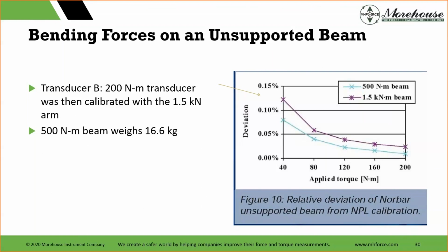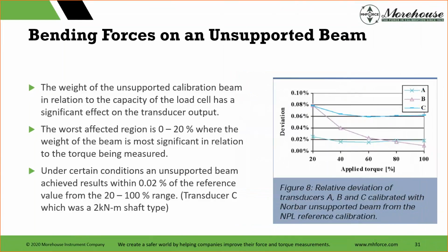That's the weight of that beam. That's when we go back to the types of standards. It's where we're going with supporting a beam, which takes a lot of this away. So now let's look at the weight of the unsupported beam in relation to the capacity. The load cell has a significant effect on the transducer output. Now we're back to that original. The worst affected region is 0 to 20%, where the weight of the beam is most significant in relation to the torque being measured. Under certain conditions, an unsupported beam achieves results within 0.02% of the reference value from the 20 to 100% range. And that was the transducer C, which is a 2 kilonewton meter shaft type.